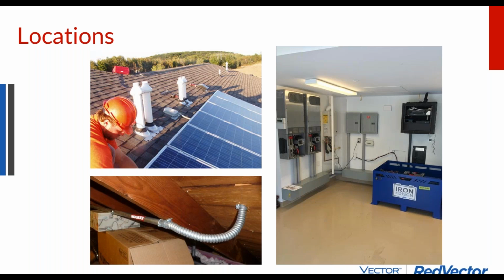The main error that I see with locations is that solar installers use a lot of metal EMT conduit, and that's because it's good physical protection and it's commonplace. And if you go into the building, you need to be in metal. The problem is the box stores like Home Depot, they don't sell the rain tight EMT connectors. And so that sometimes can be a special order item. But essentially, every generic piece has a twin, and you can get a rain tight 1-inch EMT connector, or you can get a standard 1-inch EMT connector, which is not rain tight.